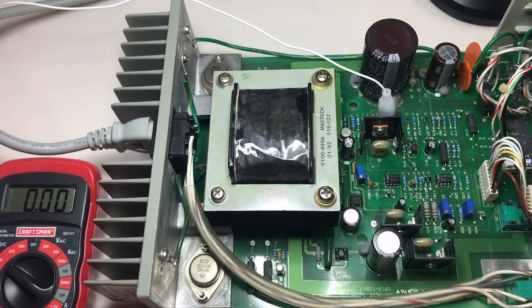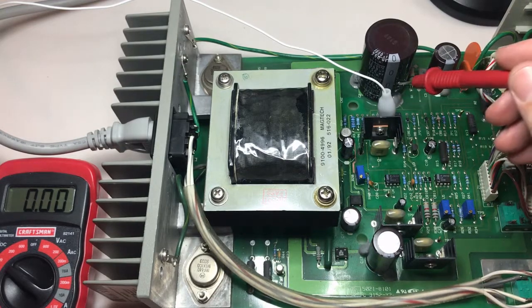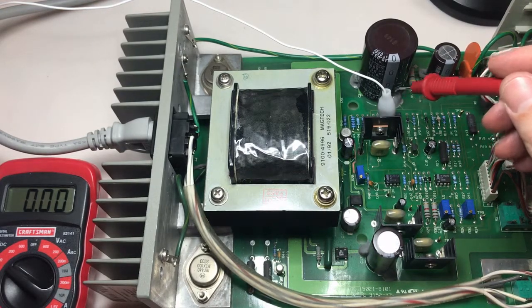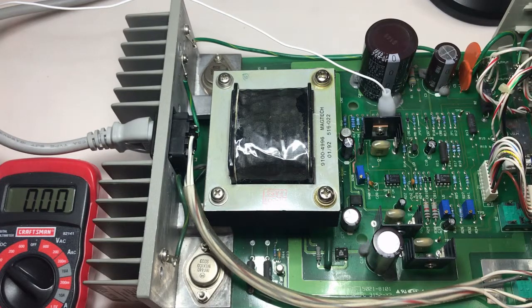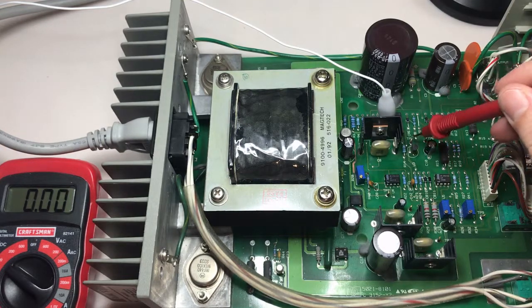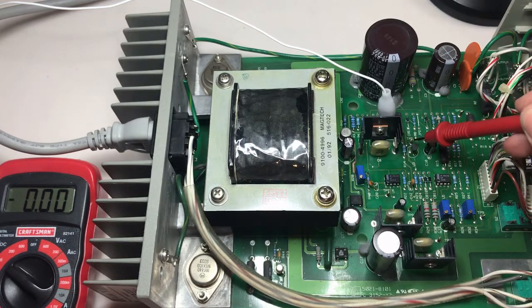I have the jumper here from test point 1, which is positive 12, so I'm going to go to test point 5, which is positive 5. We should have a 7 volt signal here. Test point 5 is right here... and nothing. That's no good.